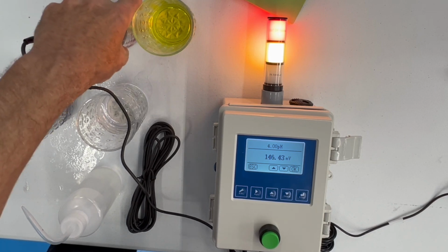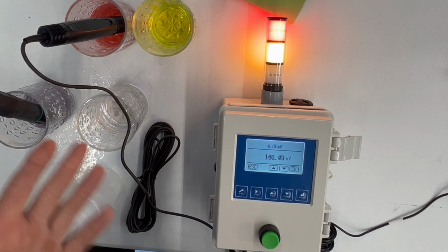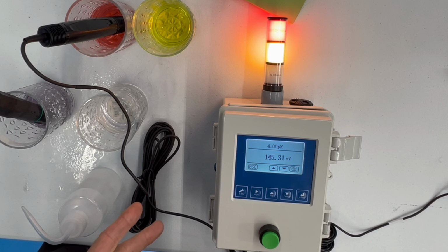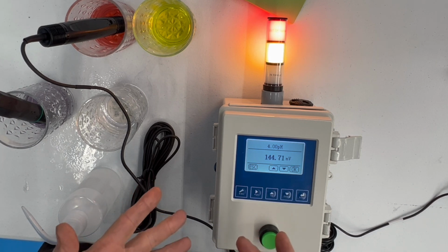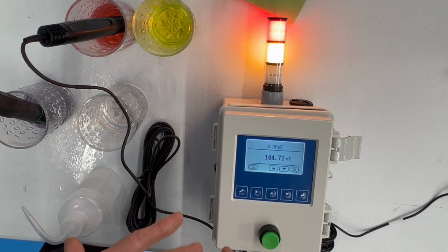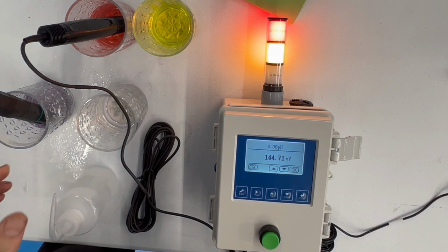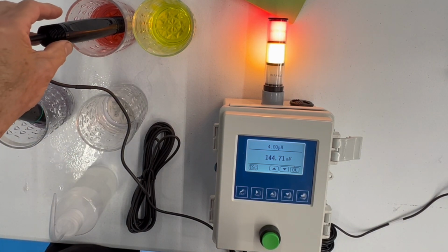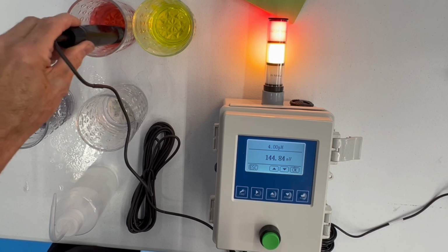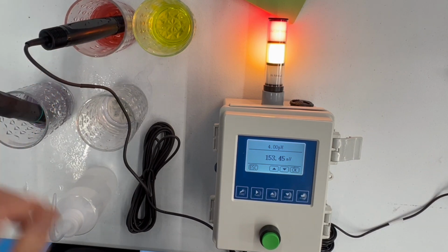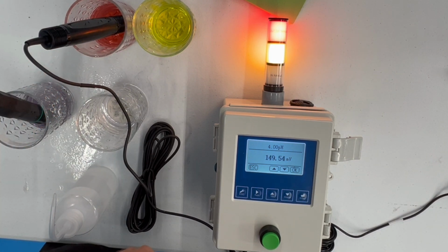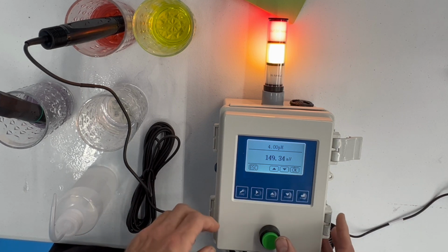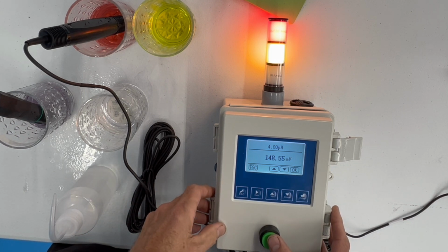On these industrial pH probes, the either glass or antimony is thicker than a laboratory probe that you might be used to, and that's to resist abrasives and dropping and bumps that could happen in industrial online monitoring applications. So it takes longer to calibrate. Anyway, we're going to let it stabilize, and it looks like around 150 is where it wants to settle in. So we'll say okay to that.